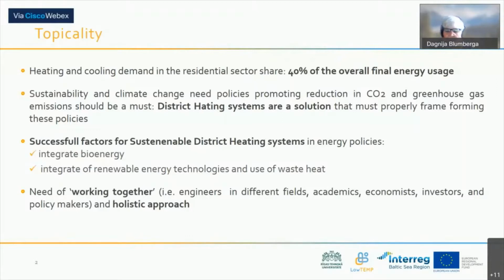One of the main added values is that we got a lot of nice friends in municipalities. We got a lot of interest about this project, and when it was realized we arranged seminars where the Latvian District Heating Society were all very interested in the results. The main problem was that from an engineering viewpoint, we suggested they change boilers from 1 megawatt to only 200 kilowatts, and it was very hard for them to believe this would be enough.